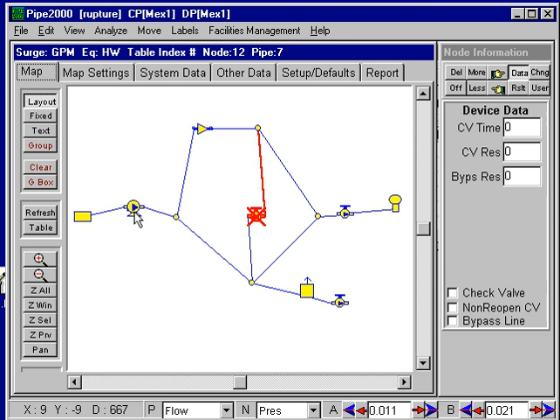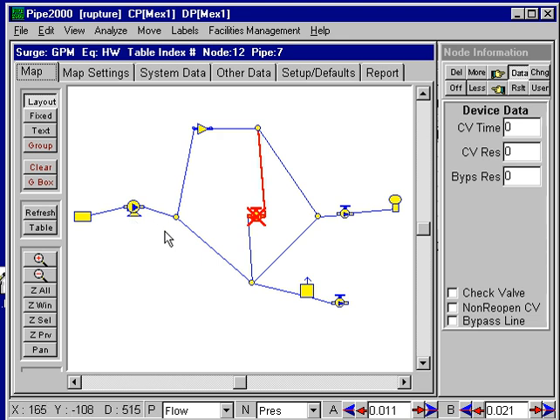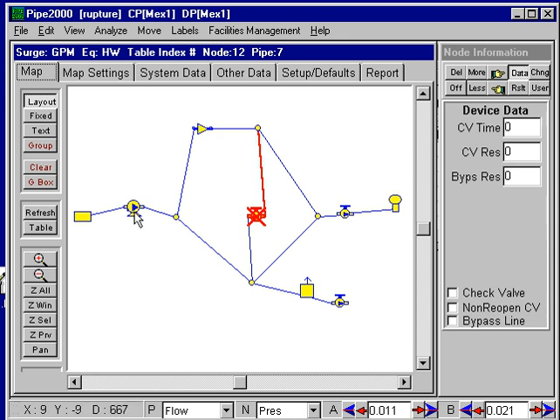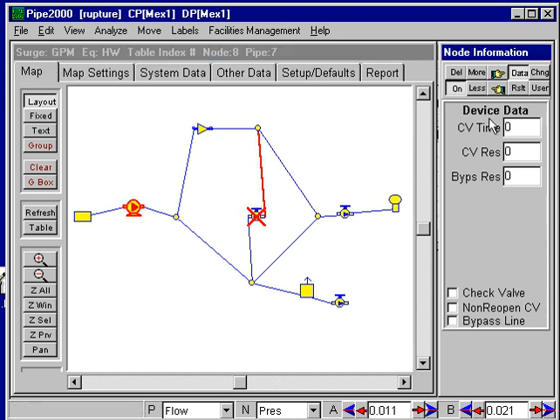For this pump in Surge 2000, there's not assumed to be a check valve. If a pump doesn't have a check valve and the pump speed ran down, because of this tank you'd get reverse flow through the pump. So if you want a check valve in Surge 2000, you have to select that pump, indicate that there's a check valve in there, and provide the required information.